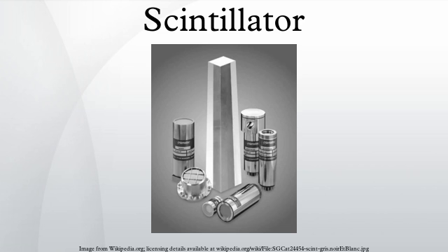Ruggedness and good behavior under high temperature may be desirable where resistance to vibration and high temperature is necessary. The practical choice of a scintillator material is usually a compromise among those properties to best fit a given application. Among the properties listed above, the light output is the most important, as it affects both the efficiency and the resolution of the detector. The light output is a strong function of the type of incident particle or photon and of its energy, which therefore strongly influences the type of scintillation material to be used for a particular application.